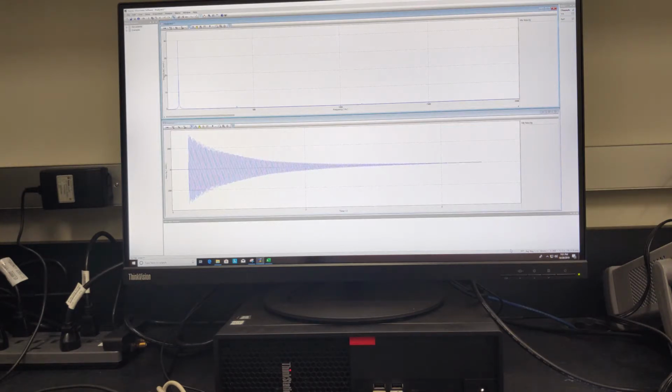The second strike is also pretty smooth. The indicator of the trigger is on again, then another one. Keep each strike at the same strength, with the magnitude of each strike within 100 millimeters per second to 500 millimeters per second, then you may get a pretty decent waveform.